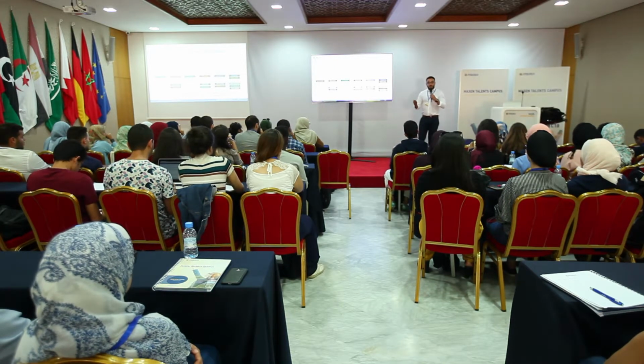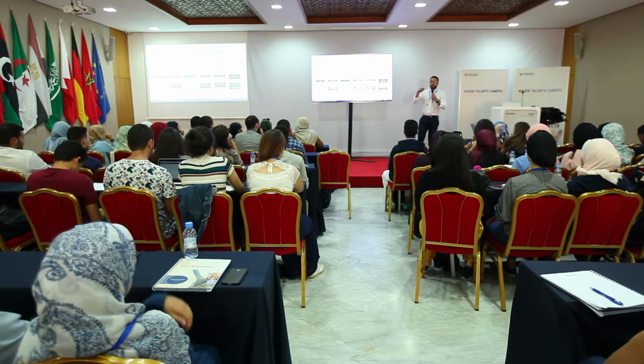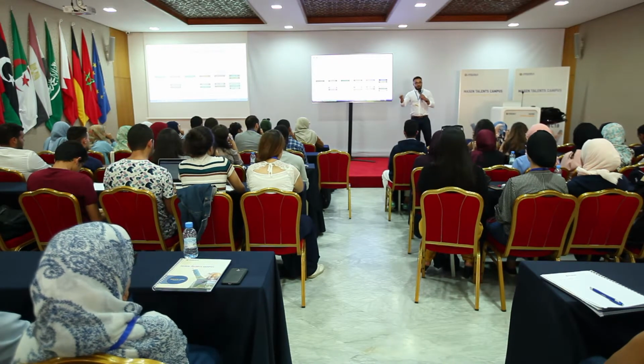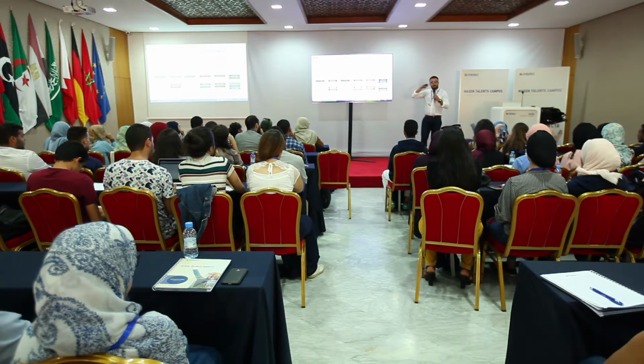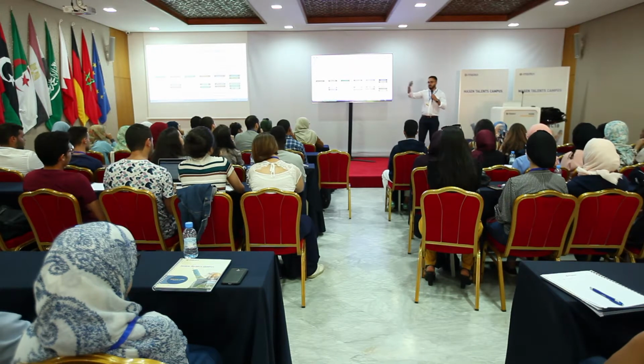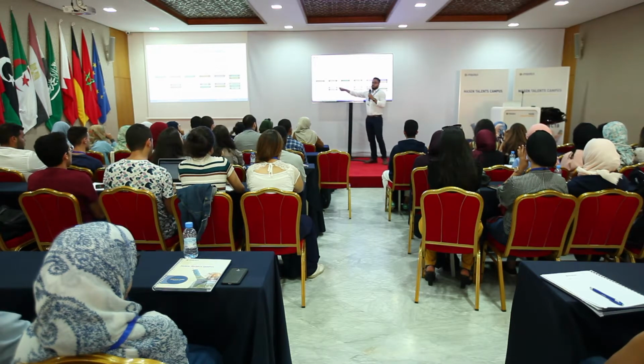On this side, it's the same. What should be the rated power, the thermal power of my receiver? How large should the storage tanks be? What should be the effectiveness of my heat exchangers? Meaning, how large should they be? Of course, like in any heat exchanger, the larger the area, the more energy they will deliver. But the larger the area, the more costly they are.